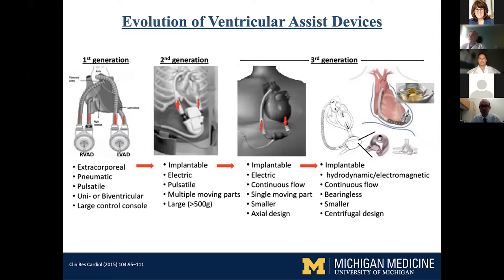The next big iteration was continuous flow, introduced with HeartMate II. People realized you don't really need pulsatile flow, and that allowed a simpler rotary mechanism — whether axial or centrifugal — to provide flow. By the mechanics alone, you could design a pump that was much more reliable and less apt to fail. The HeartMate II with its axial design still had problems — pump thrombosis, pump exchanges, strokes — though it was obviously much better than the previous generation.